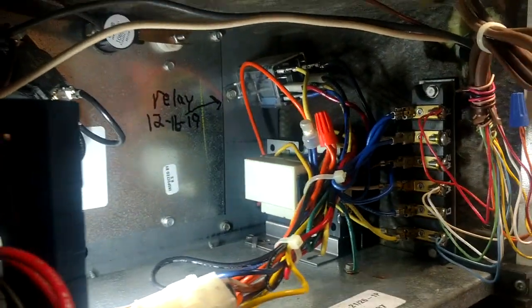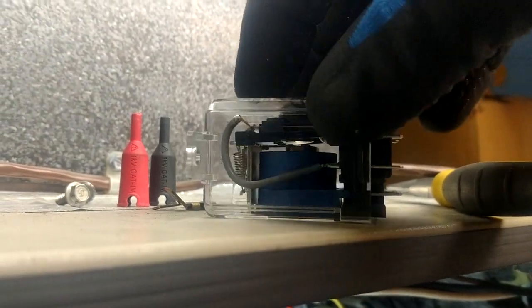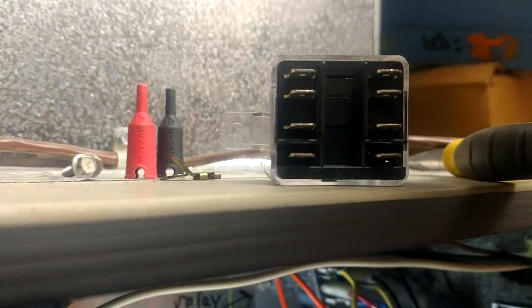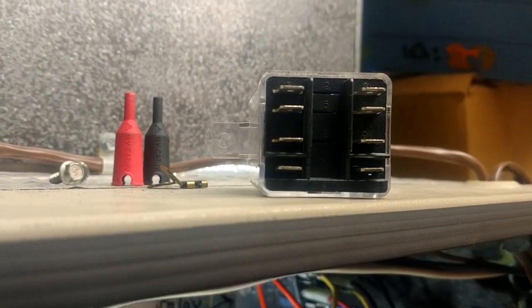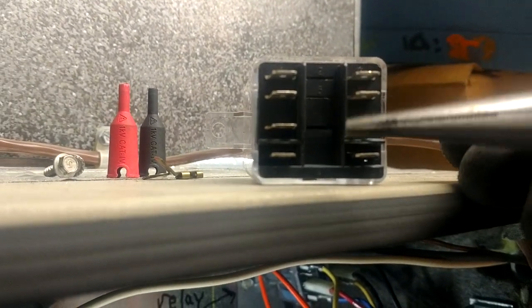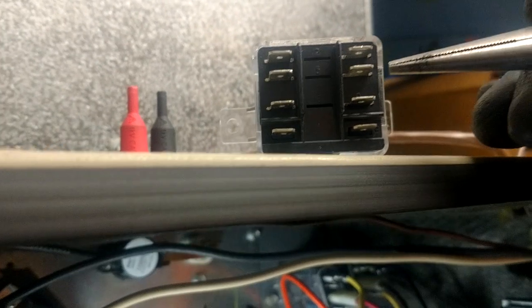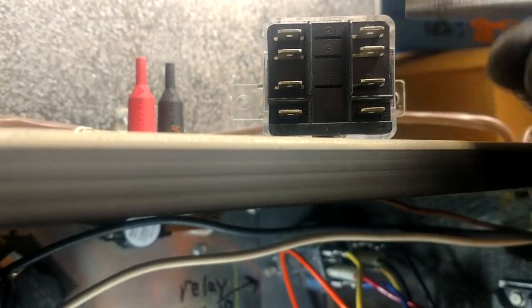I've got a replacement up here because I know the thing's bad, but I thought I would film a video on it. On these ice cube relays, this is a double pole double throw - you've got two identical sides here. This is kind of like your all-purpose White-Rodgers brown relay but in a different configuration, and you have your two sets of identical contacts.